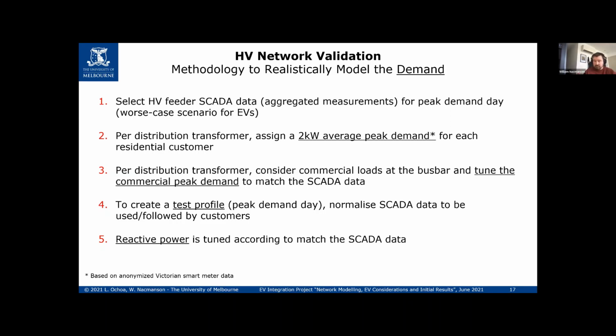Then to check everything is sensible in a time series manner, we create a profile for the loads to follow. We do this simply by normalizing the power profile that was measured at the head of the feeder, and we apply that profile to all the customers. Then we can run power flows across the 24-hour period of our measurements. And finally, we look at the reactive power. If there are any differences in reactive power, we can make some adjustments to our model so that it matches. And then we have a sensible feeder that matches up with what's being measured in reality.